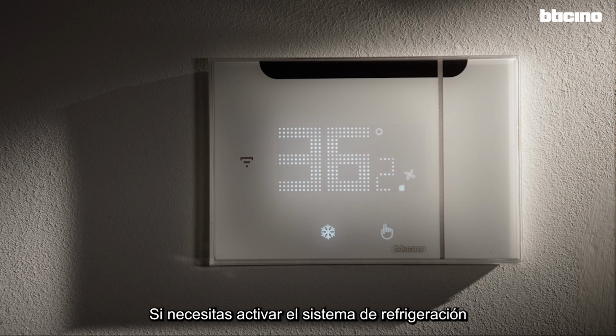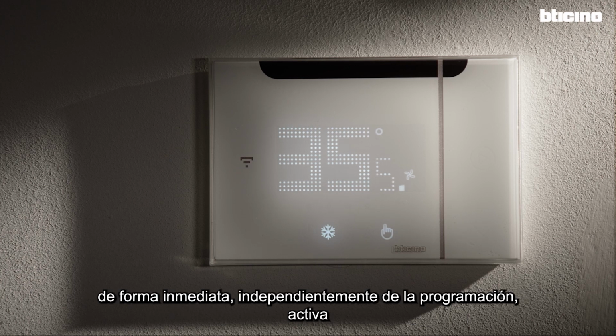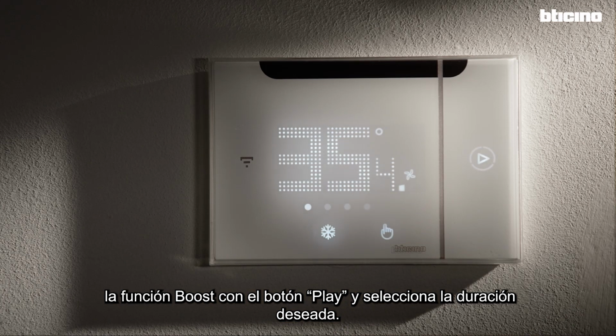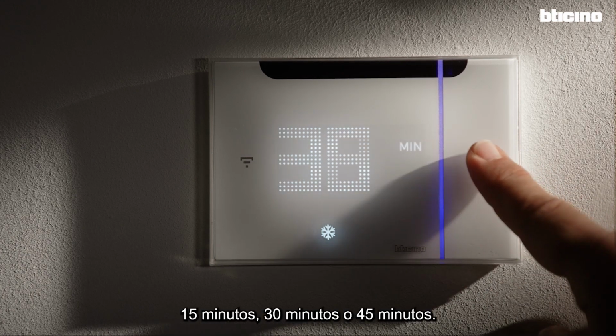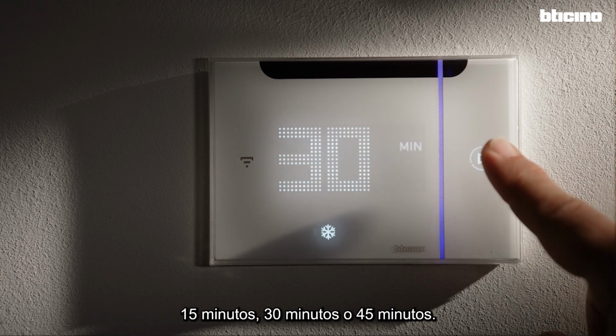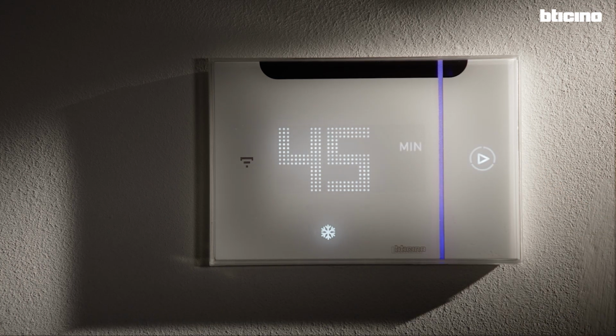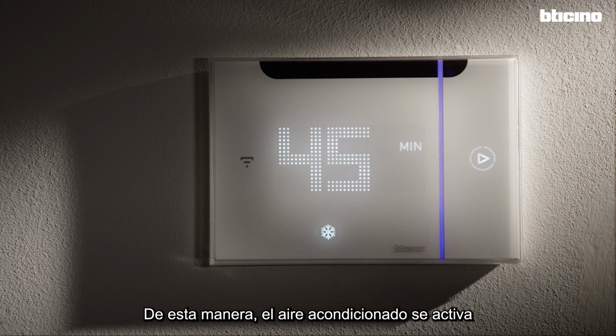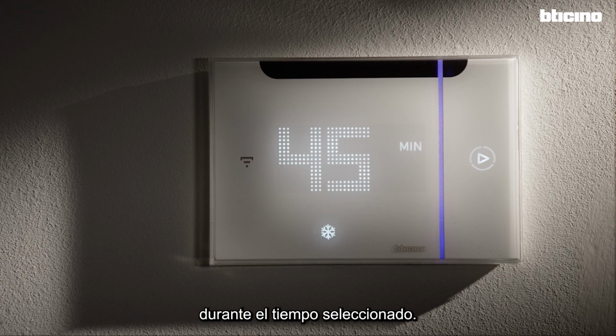If you need to turn the cooling system on immediately, independent of the schedule, activate the boost function with the play button and select the desired time: 15 minutes, 30 minutes, or 45 minutes. In this way, the cooling system will activate for the selected duration.